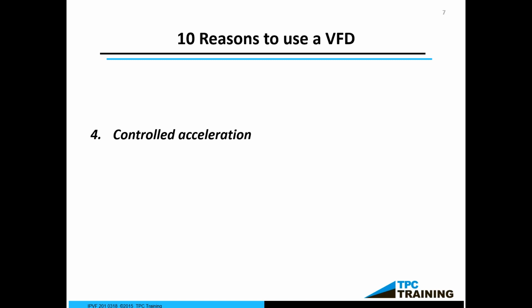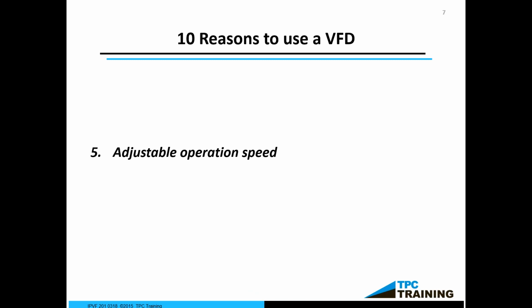Control acceleration. Each application is going to be a little bit different. If you're a ski lift, for example, you want to slow your acceleration, maybe from zero speed to full speed, and take 45 seconds. But if you're operating a pump or a blower, you can change that acceleration to 3 seconds. So controlling the acceleration is very easy to do. Adjustable speed, maybe you want to operate it by hand. Maybe it's a conveyor. You'll be able to control it either at the keypad or by remote operation, depending on the application. You'll be able to set these things up very easily.